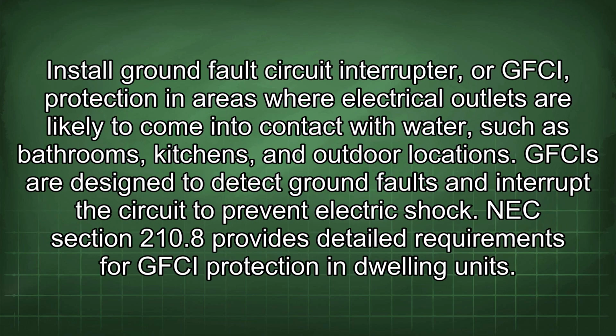Install ground fault circuit interrupter, or GFCI, protection in areas where electrical outlets are likely to come into contact with water, such as bathrooms, kitchens, and outdoor locations. GFCIs are designed to detect ground faults and interrupt the circuit to prevent electric shock. NEC Section 210.8 provides detailed requirements for GFCI protection in dwelling units.